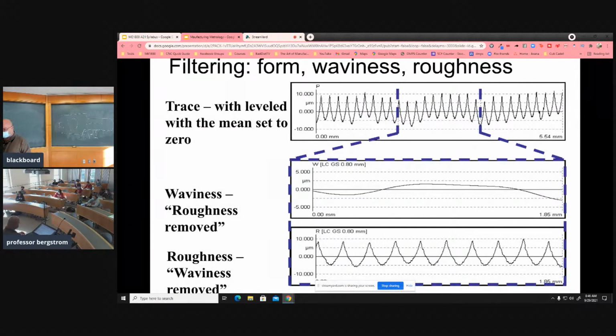Yeah, this is an example of filtering the waviness. So that's the profile that we had the picture of before. It's been leveled. We take that long wavelength out, and we're left with that roughness profile. By changing the filtering parameters, we can change the measured values by 41% for RA. So if you're specifying RA on your print, it's not sufficient. You also need to specify how to do the filtering to separate the waviness from the roughness.